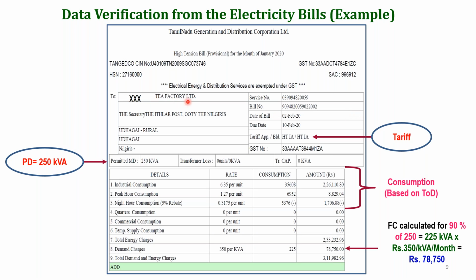Now, this is a tea factory electricity bill, a portion of the first page of the electricity bill, where the permitted demand is represented here. This company got a permitted demand, sometimes also represented as sanction demand. So the sanction demand is 250 kVA. So therefore, this company should operate within 250 kVA only. If it crosses beyond 250 kVA, it is automatically penalized with an EDC penalty. And it is in the category of 1A. 1A is the representative category for industries in Tamil Nadu.